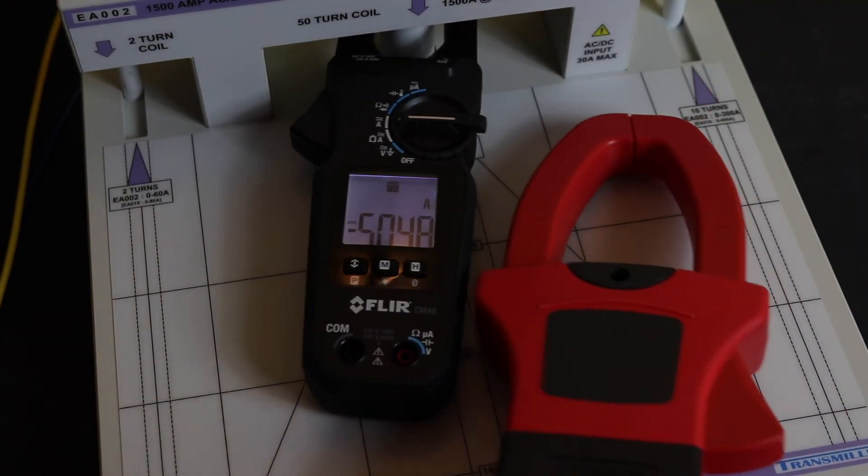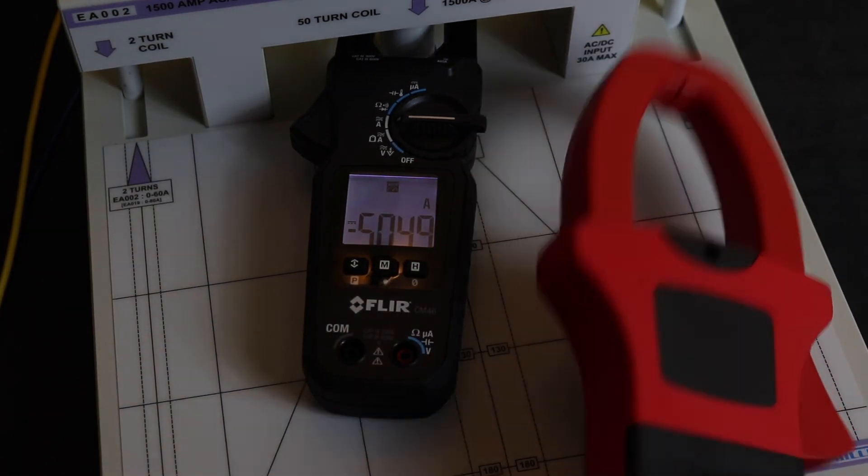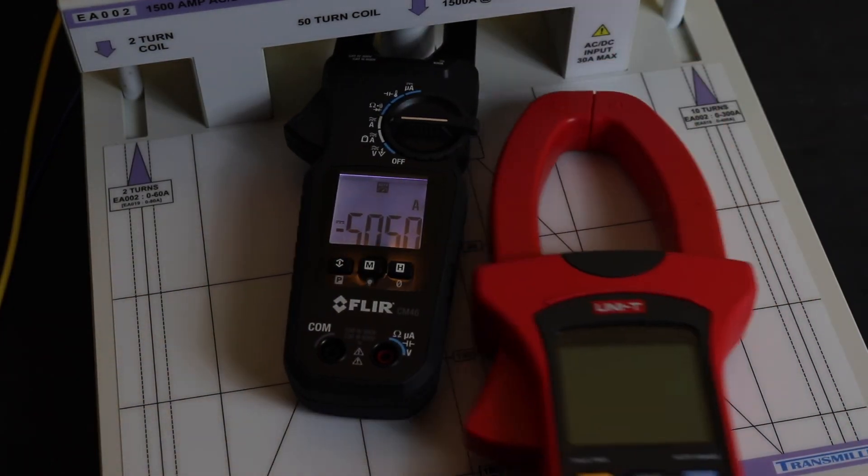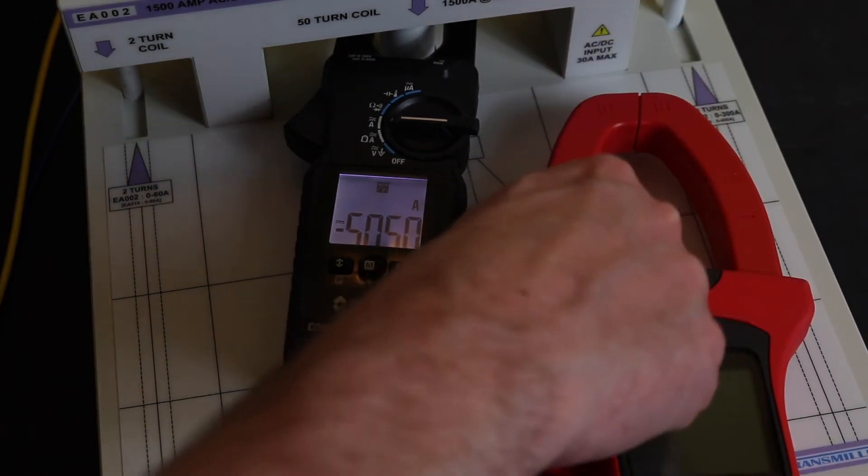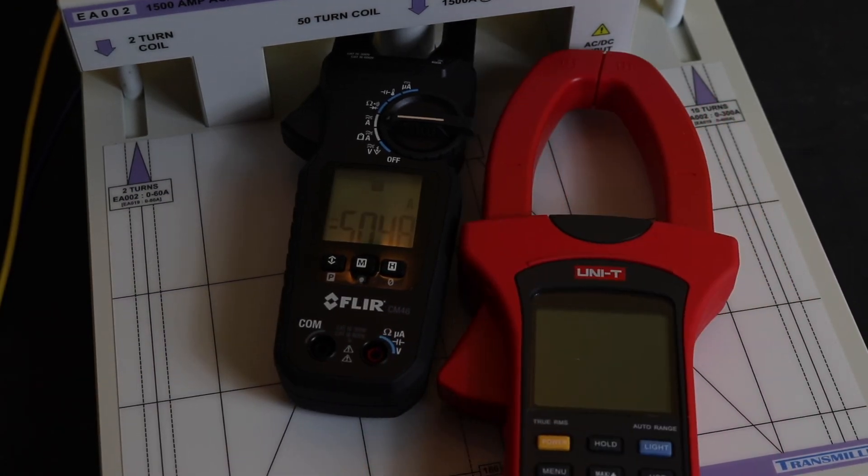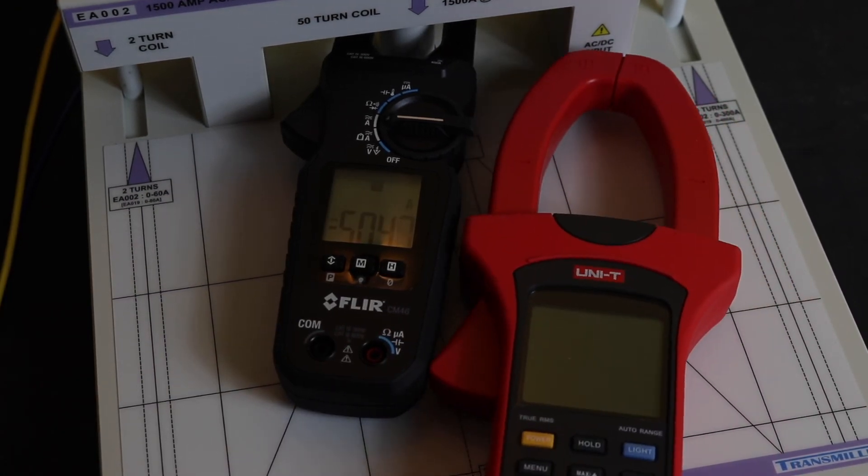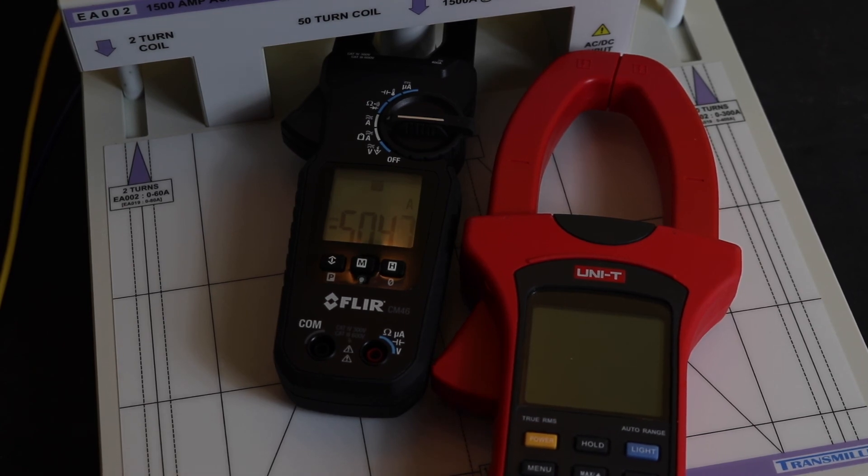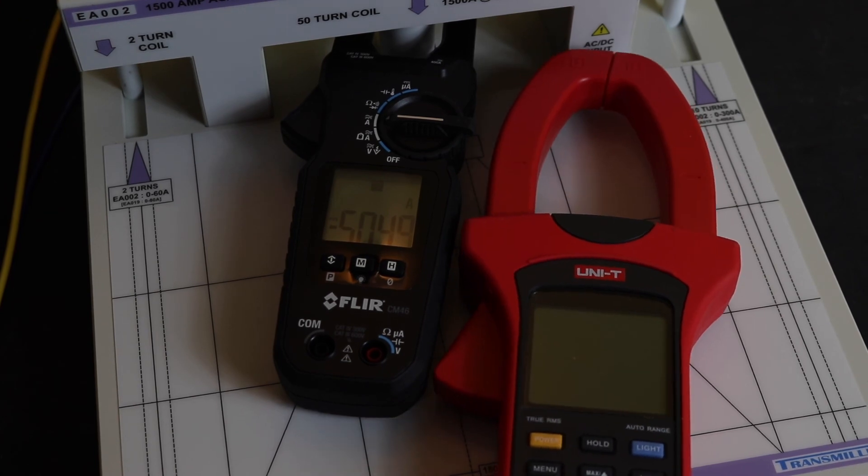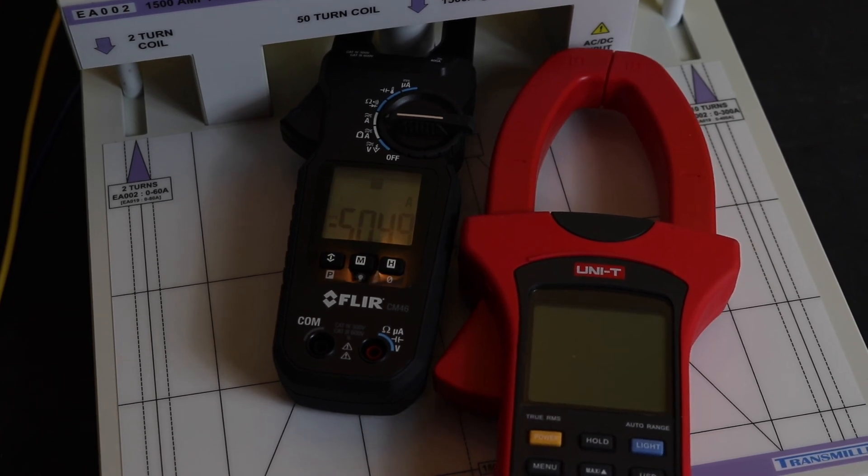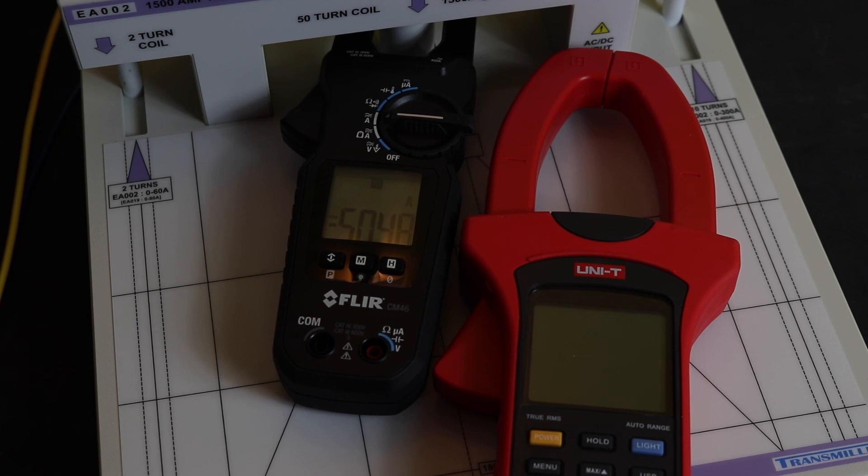instrument, I guess, along with the actual measurement of the phase-to-phase voltage only picking up two phases. To be honest, it's a little bit disappointing. I don't think I'd recommend anybody to go out and buy that. I think you'd be better off saving your pennies and getting a proper three-phase power meter. Some of them you can pick up reasonably cheap these days, but yeah, that's got issues.